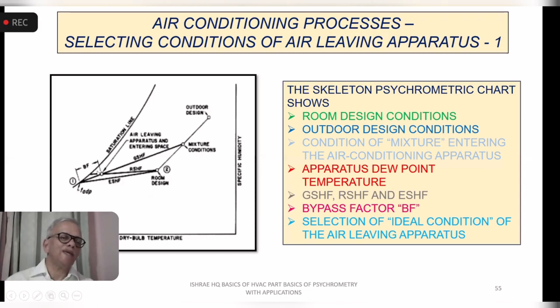So if you supply the air at this condition, it will have a capacity to pick up the room sensible as well as latent, because it is following on this sensible heat factor line. So once it picks up the sensible and latent, it will end in this, provided you have done the calculation right for the air quantity CFM.